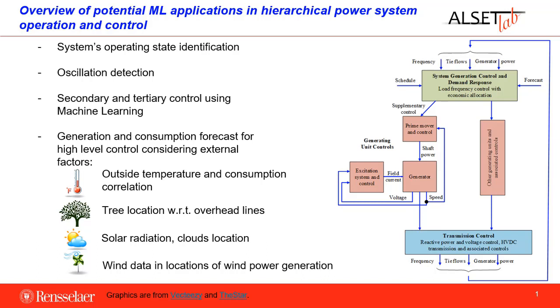Demand response balances the loads to smooth out the peaks of power demand. These controls are complemented with transmission controls that perform reactive power and voltage control, activating static var compensators, switchable reactors and capacitors, and tap-changing transformers — some of these controls activated by operator. At each level of power system operation and control, machine learning can be of use, combining available knowledge about the power system and including external factors such as outside temperature, tree location, solar radiation, and wind data. Machine learning can help identify the system's operating state, detect oscillations, perform decision making at higher-level control, and provide generation consumption forecasts using historical data.